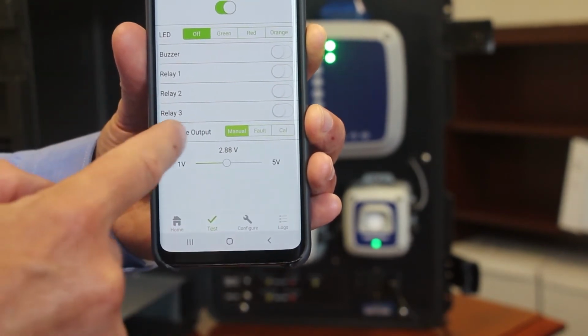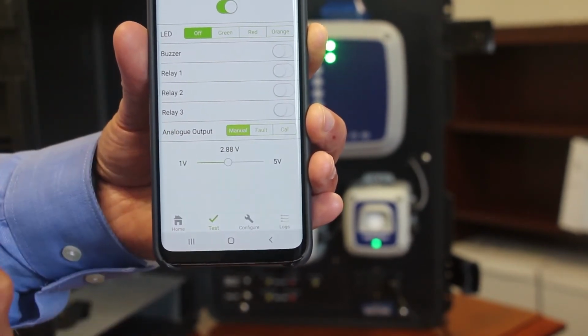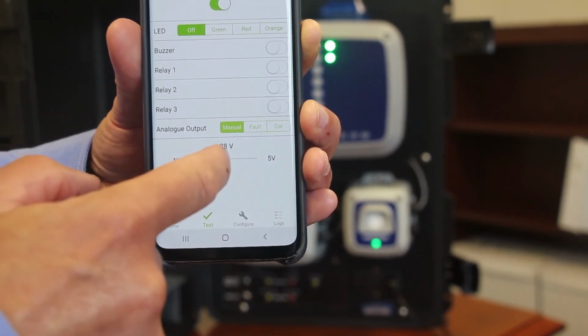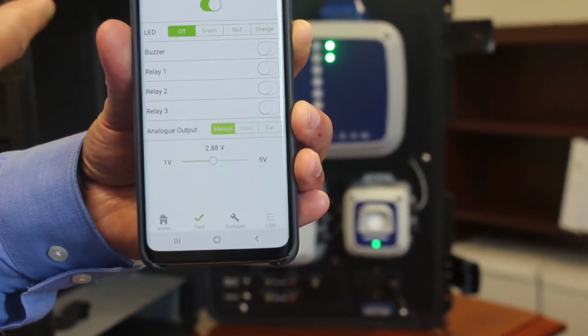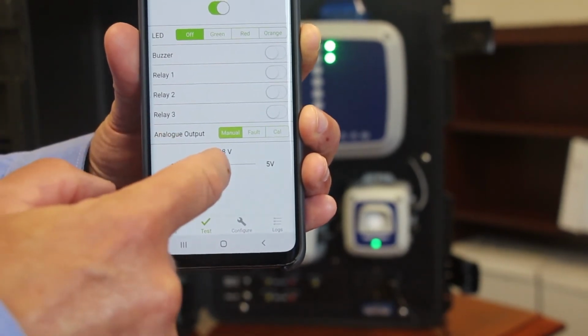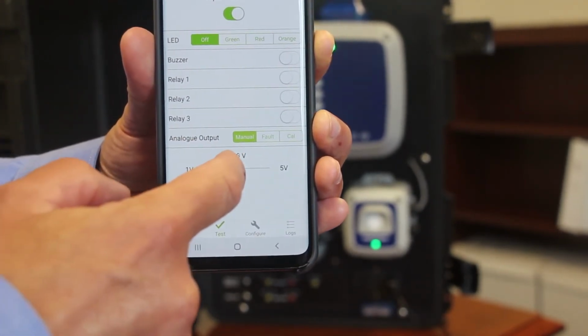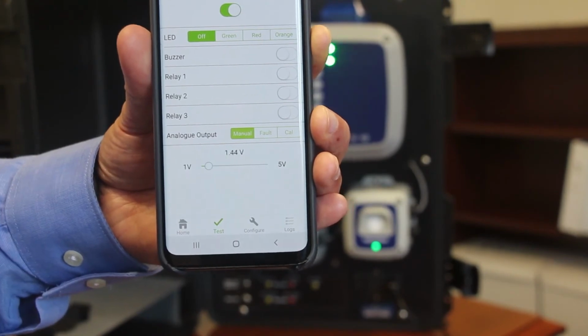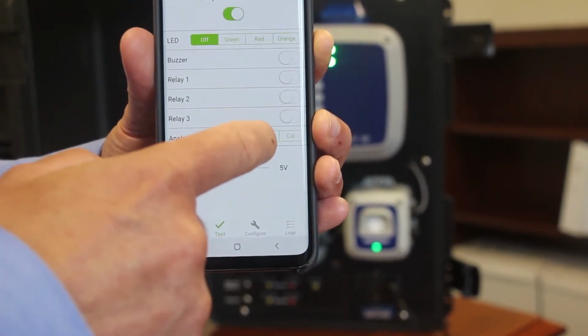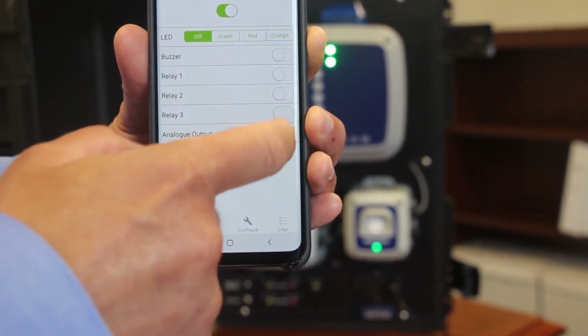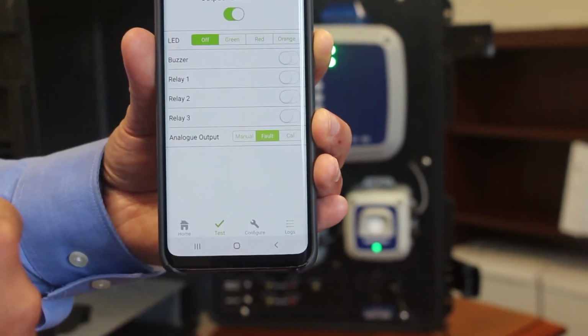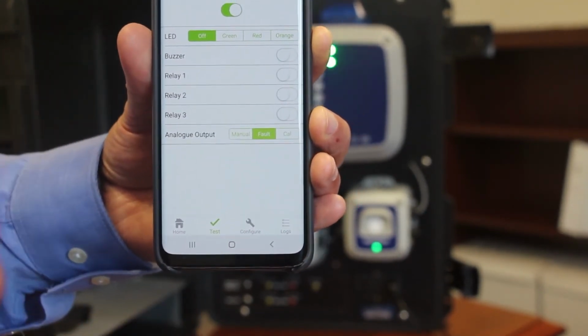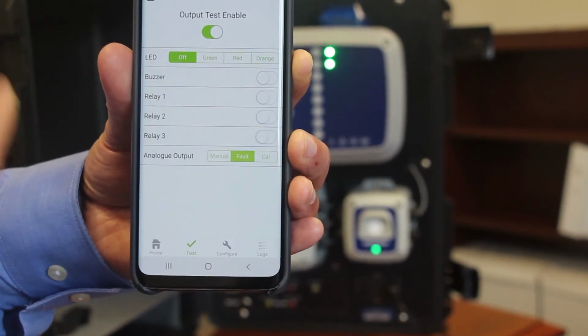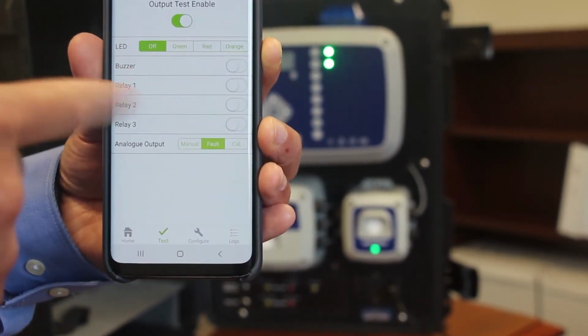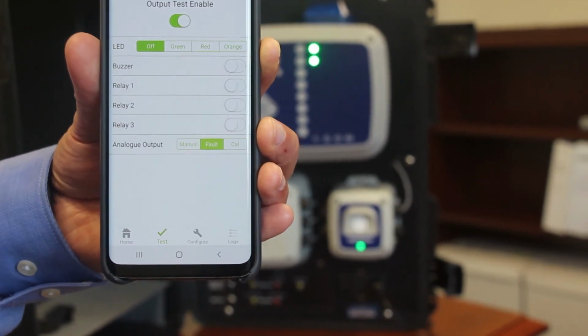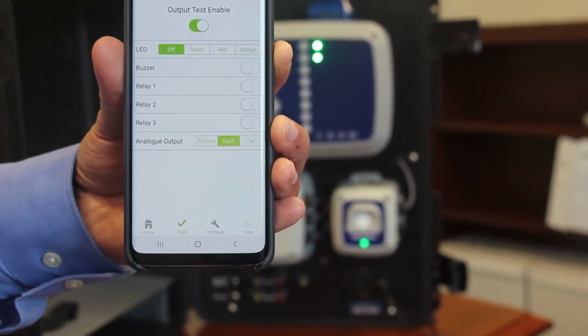Okay. And then the final item on here is your analog output tests. So if you have something connected to the unit through the analog output, using this simple slide gauge here, you can activate and run the analog signal. You can do that for the fault as well. So it's a very useful diagnostic tool. If we move across to the demo unit, I'll flick through some of these options and you'll see how that's demonstrated on the unit itself.